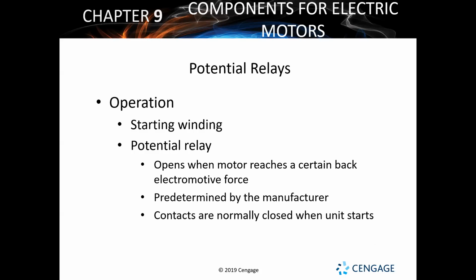Start windings, again, remember, they're going to be taking in all that extra power, bringing all that electricity into the system. That way it can start up. So the potential relay opens when the motor reaches a certain back electromotive force. When it's got that back voltage feed from that start winding, it'll decide, okay, yep, we've got enough, we're good. Let's go ahead and disconnect that start winding, allow the run winding to take over from here.